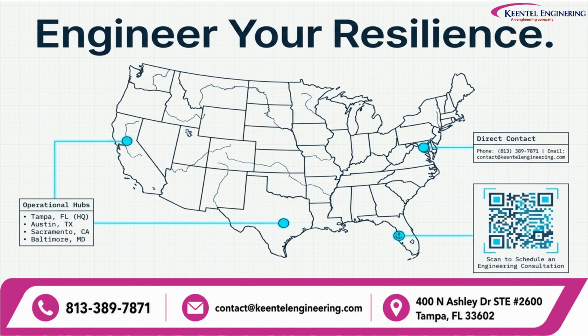Engineer the protection before the fault occurs. Validate the models. Coordinate the protection. Test the hardware. Verify the trip path. And build a system that is prepared for its worst operating condition. Because when a critical transformer is under fault, there is no opportunity to redesign the protection system. It has to work the first time. Engineer your resilience.